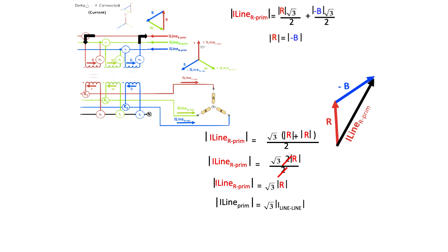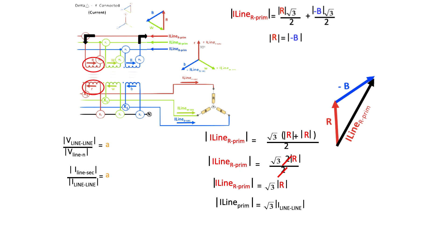Looking at the turns ratio of the individual legs of the transformer, we can define the turns ratio by looking at the ratio of the line-to-line primary voltage over the line-to-neutral secondary voltage, and we'll equate that to A, which is the turns ratio of the individual leg of the transformer. And we know that if current is flowing in the transformer, the turns ratio would be defined by just the inverse of that — which is the current flowing in the secondary line over the current flowing in the primary line-to-line. Now we're talking magnitudes here, because the ratio is a magnitude.